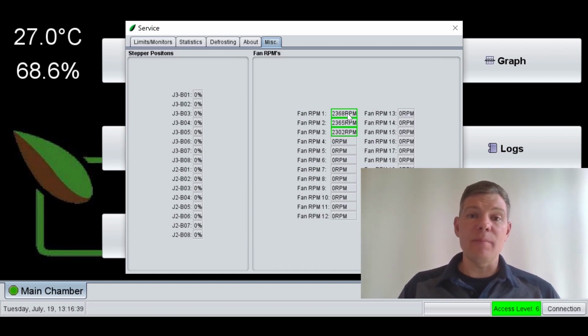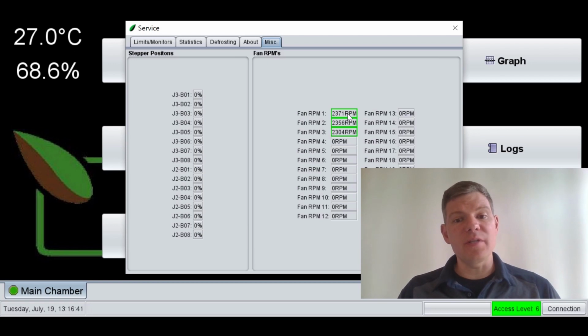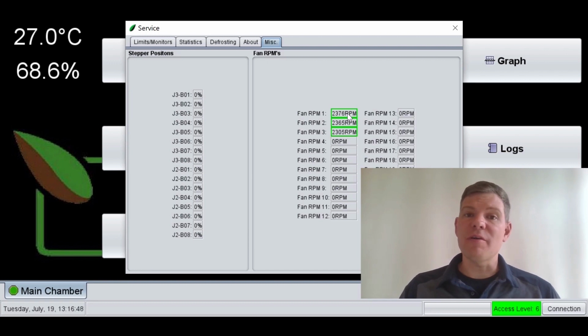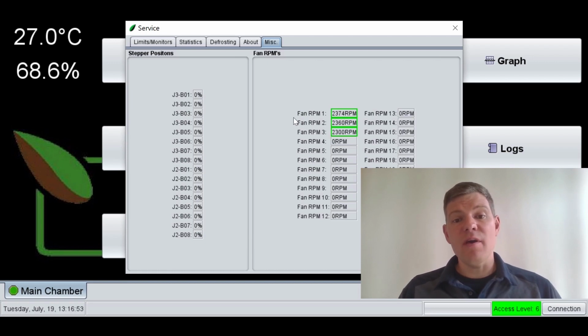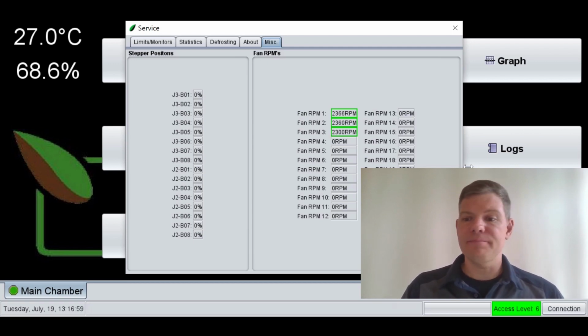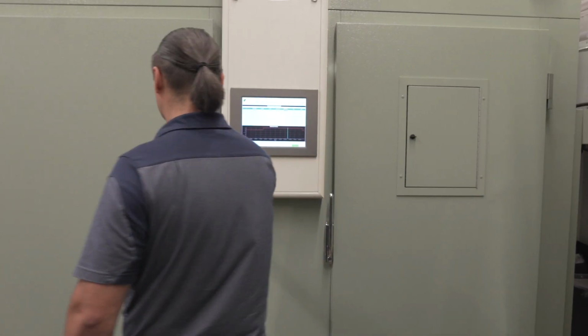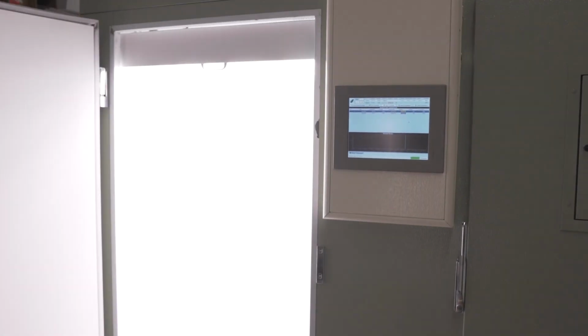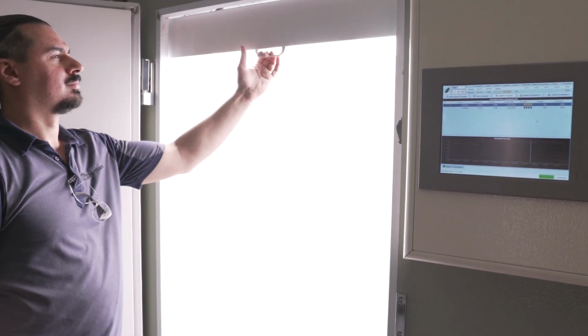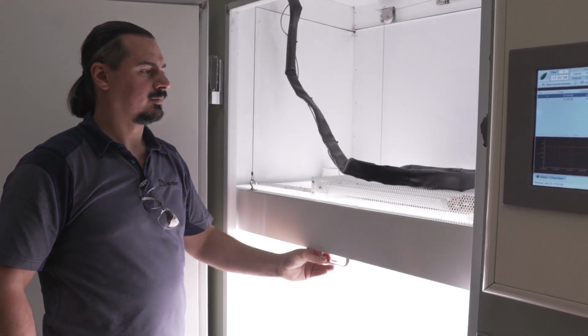If the fan RPM drops below 1000, it will turn yellow, and red when 0. If fan RPM drops below 1000, it will trigger a fan speed alarm and your fans will need to be replaced. If you cannot see fan RPM status in your VNet software, your circulating fans must be checked visually. Please contact us for how to access the circulating fans in your chamber and be sure to follow all safety protocol outlined in the Operation and Maintenance Manual.